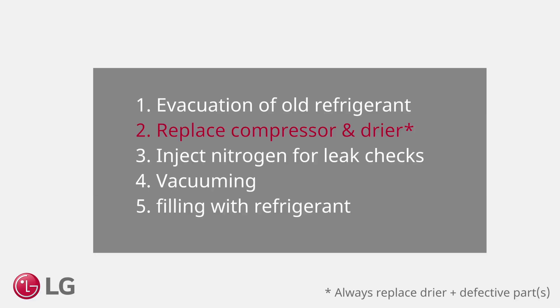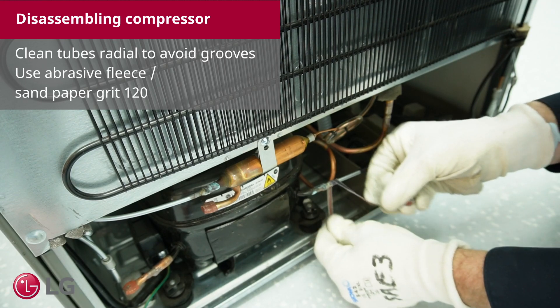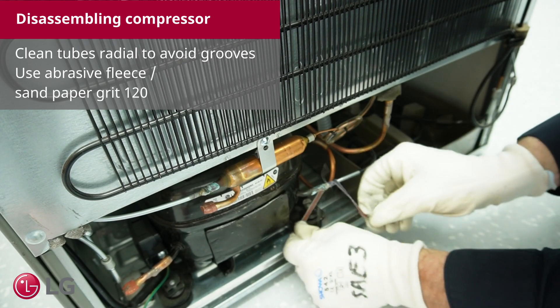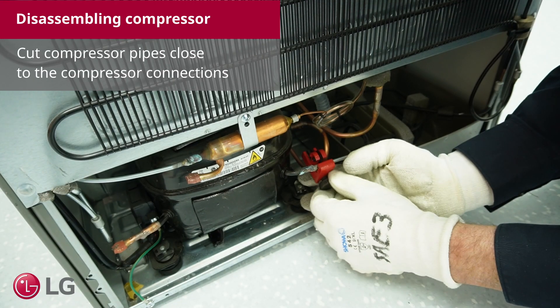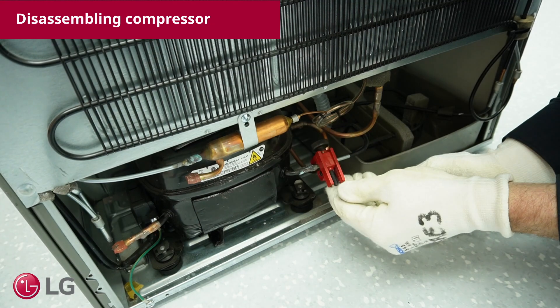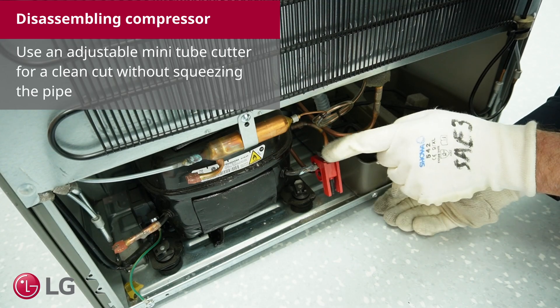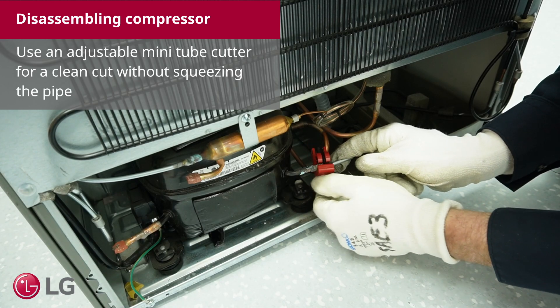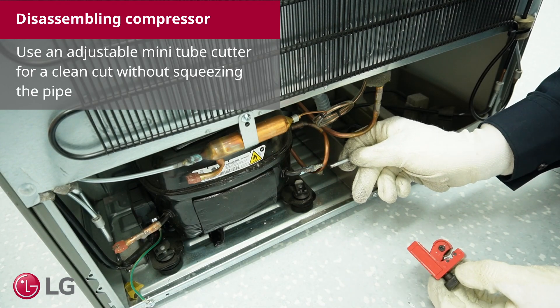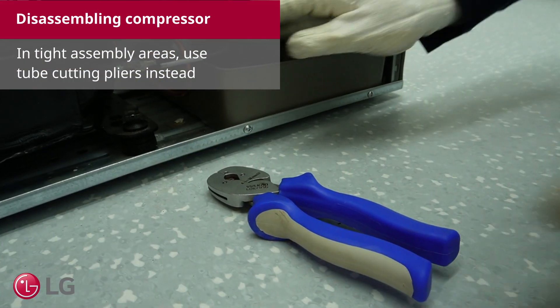Replace the compressor and dryer. Clean all tubes radially to avoid grooves — use abrasive fleece or sandpaper grit 120. Cut the compressor pipes close to the compressor connections. Use an adjustable mini tube cutter for a clean cut without squeezing the pipe. In tight assembly areas, use tube cutting pliers instead.